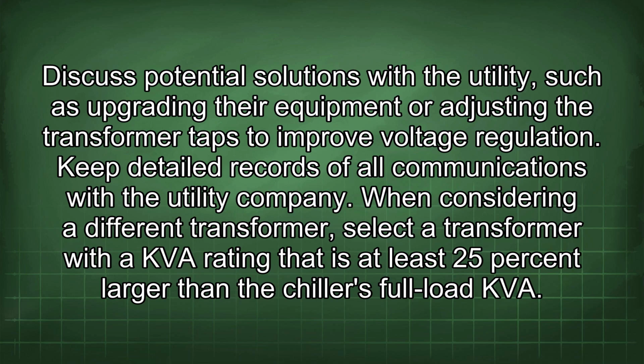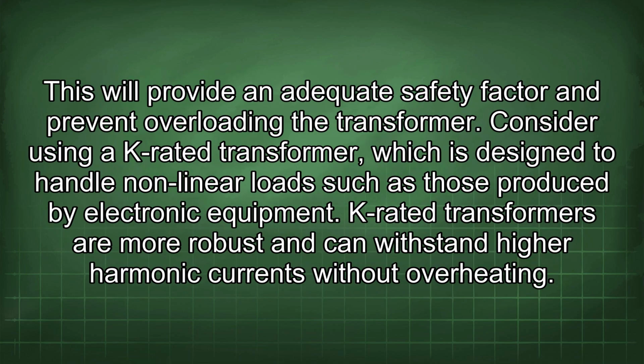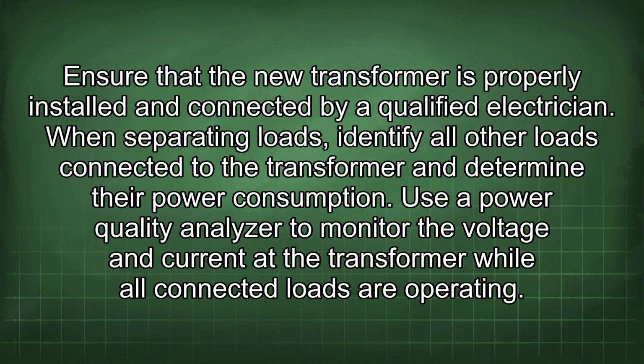When considering a different transformer, select a transformer with a kVA rating that is at least 25% larger than the chiller's full load kVA. This will provide an adequate safety factor and prevent overloading the transformer. Consider using a K-rated transformer, which is designed to handle non-linear loads such as those produced by electronic equipment. K-rated transformers are more robust and can withstand high harmonic currents without overheating. Ensure that the new transformer is properly installed and connected by a qualified electrician.